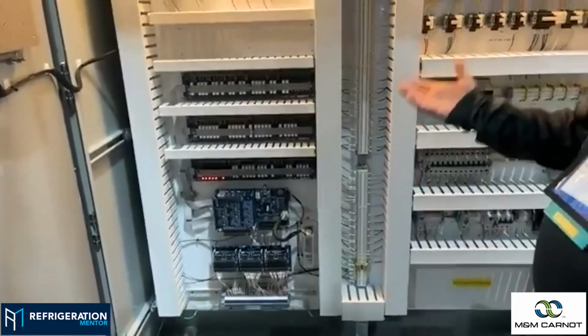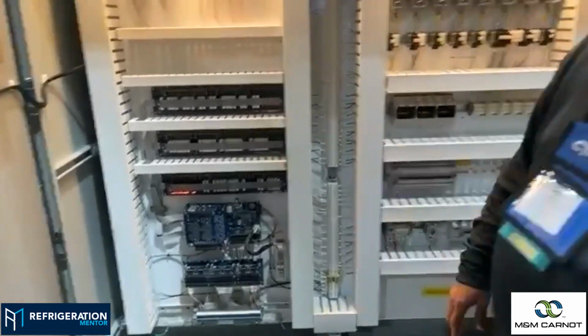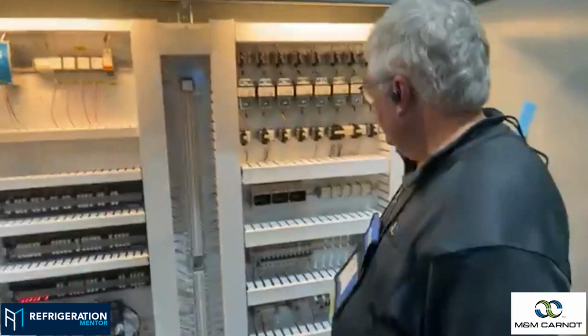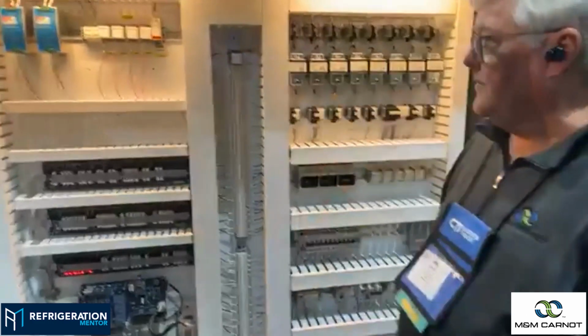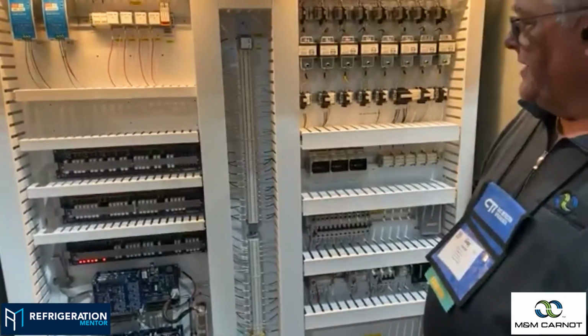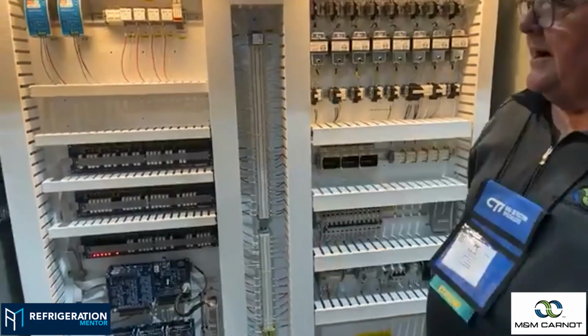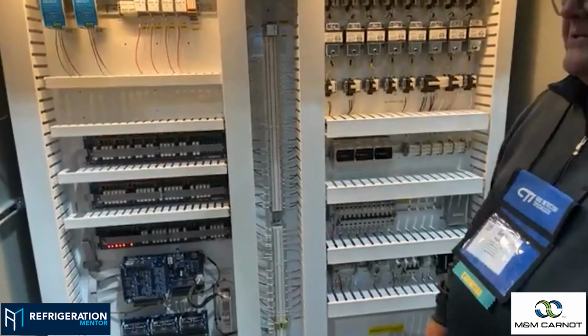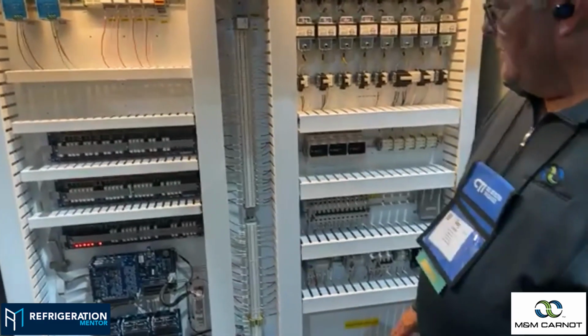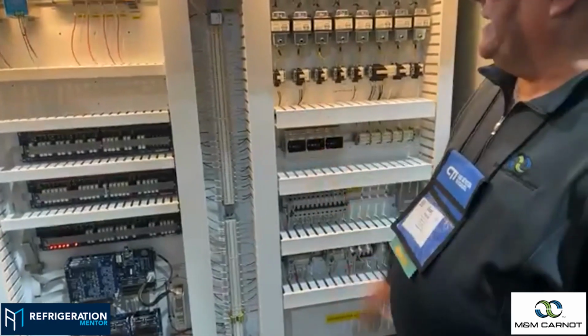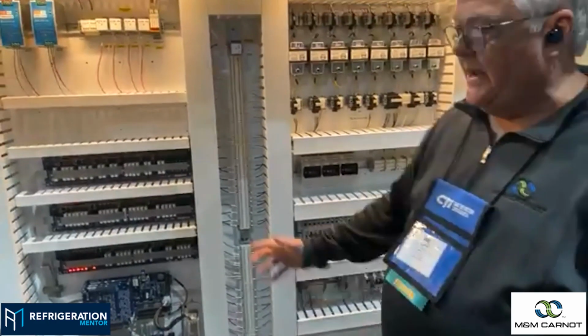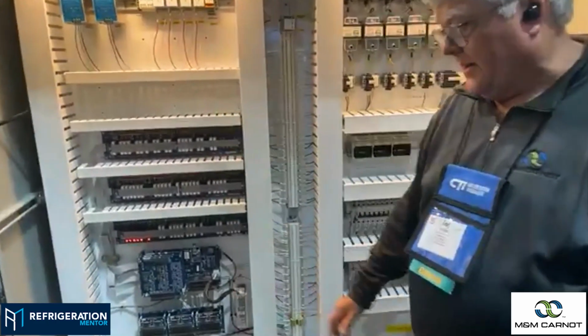Valves are smaller but move a lot slower because of the pressure differential. Stepper motors are used for superheat control on the evaporators and for the high pressure valves and flash gas valves. So the componentry is a little different, but pretty much the same, and we're able to do it with our standard micro.